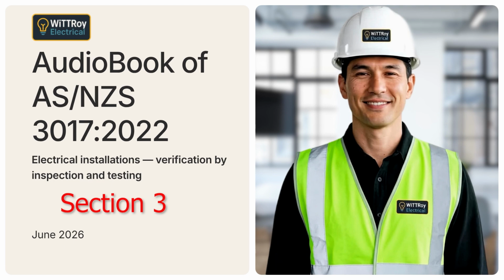Particular installation conditions must be considered. This may include locations affected by water, explosive atmospheres, extra low voltage systems, and high voltage situations. Equipment should also conform with the applicable standards and any additional manufacturer's instructions. Connection, support, and fixing must be checked. Protection against external influences must be checked, including ingress of moisture and required IP rating where applicable. The equipment must also be suitable for the intended voltage, current, and frequency. In simple terms, electrical equipment must be suitable for the job, suitable for the location, correctly connected, correctly fixed, and protected against the conditions around it.